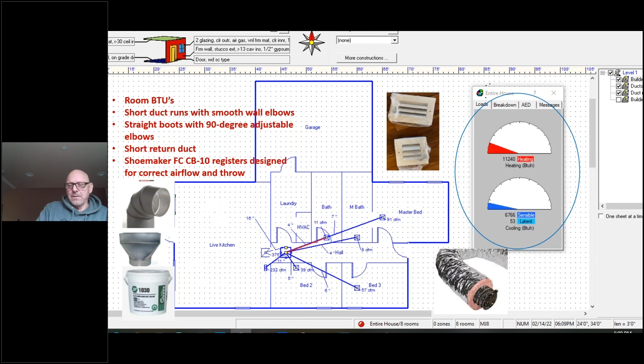So here's the equipment we chose to use. We use this 12,000 BTU Fujitsu slim duct. It's a ducted system. These systems are very sensitive to pressure. They can't push air very well, so the ductwork has to be pretty much perfect. And something I'd like to touch on, especially at Fujitsu: I use a lot of Fujitsu and I like their products. They have a lot of different variations, so we can fix a lot of projects with them. But right in here, it shows you your cooling. My cooling goes from 3,100 to 13,600, and my heating goes from 3,100 to 19,400 BTUs.